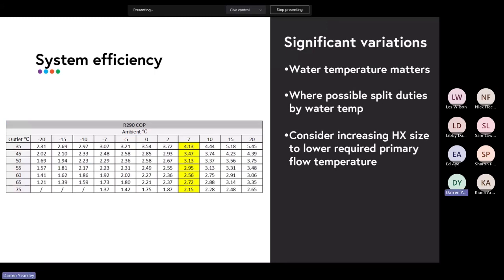So sometimes you might come into a job and they've got a gas boiler system which they need to replace, and they're thinking about doing it with air to water heat pumps. And let's say it's a classic that we see a lot: an underfloor heating application with domestic hot water. It's in your interest, it's in the system's interest to actually split that into two systems. So you can have one system which is running at low temperature all the time and another system which is running at high temperature all the time.